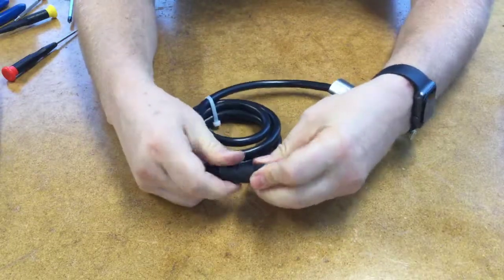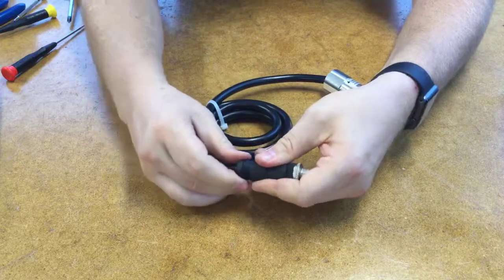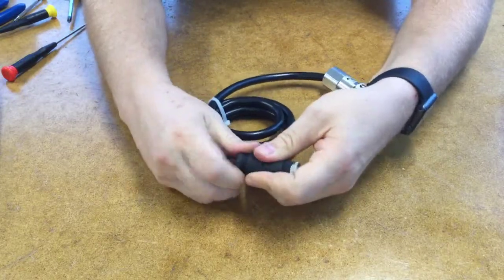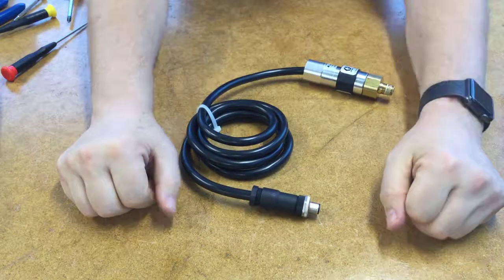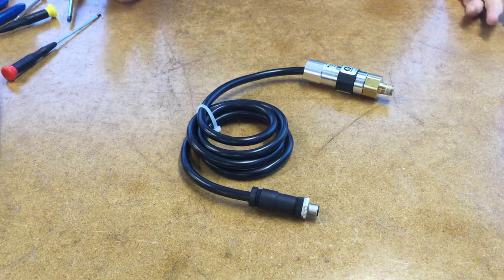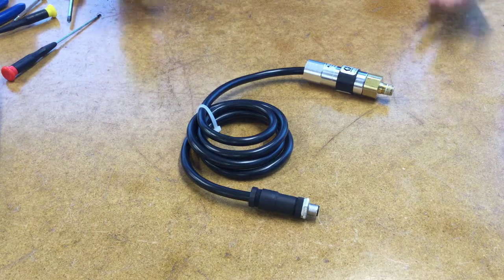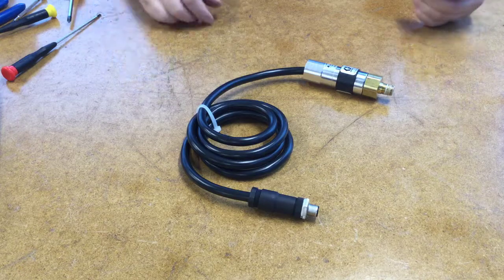And we're going to thread it all together, and when this all gets tightened up you want to just make sure that you put a wrench on there and get it nice and tight so that you're not putting tension on those wires. So that's all there is to it. This is really a very simple subject - you're just wiring up two wires and it's going to be either the blue and black wire or just pins three and four, and you look at your wiring schematic for your switch itself.